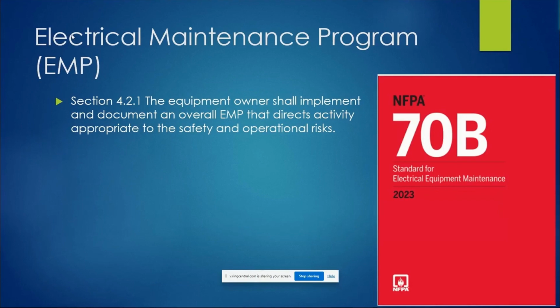You need to identify the interval at which you're going to inspect it and the type of inspection you're going to do. So, electrical vault 1, we're going to inspect it every year with an infrared scan. Then every 2 years, we'll do a housekeeping routine inspection, opening it, cleaning it, vacuuming it out, or whatever, every 2 or 5 years. That's just an example of what your program should look like. It should define all those things and what you're going to do.